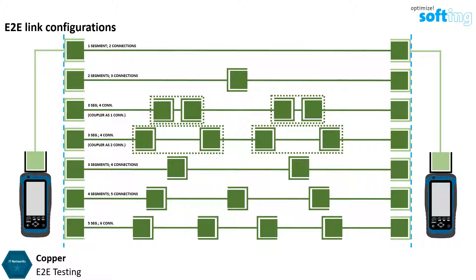For example, if 2 connections are closer than 10cm apart, they count as 1 connection. If 2 connections are more than 10cm apart, they count as 2 connections. In some configurations, segments can consist of a jack, cable and a socket, which is similar to a consolidation point. In some configurations, segments can consist of 2 sockets and a cable, which is similar to a permanent link.